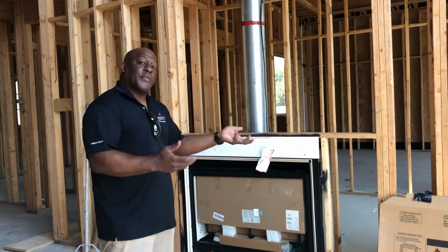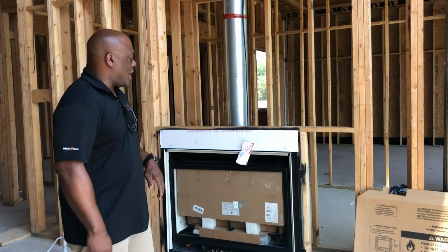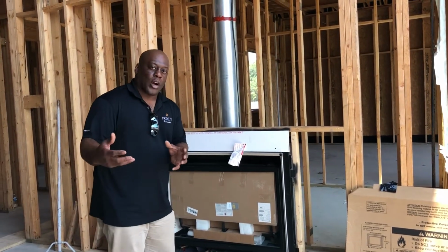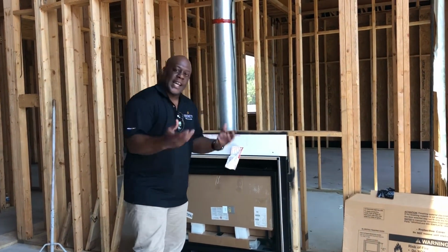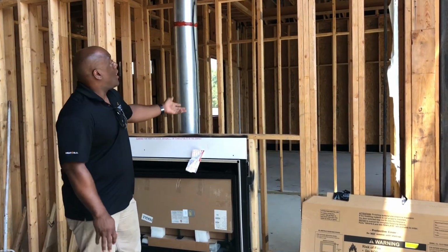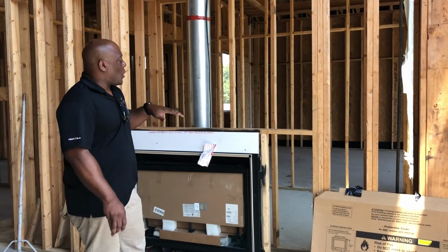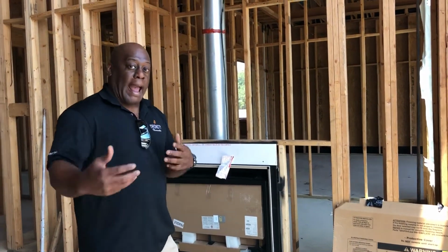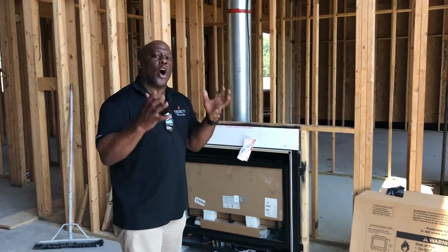So the difference between an open concept wood burning fireplace, what we're traditionally used to seeing, is that an open concept fireplace is bringing air from the room, which is typically cool, into the fireplace. It lights that, and then it pushes it up with a force called draft up through the flue pipe, and it would go straight up out of a chimney, okay? So what this fireplace does is it doesn't interact with the room as far as bringing air into the fireplace. It doesn't utilize that. The direct vent technology actually uses a coaxial pipe.